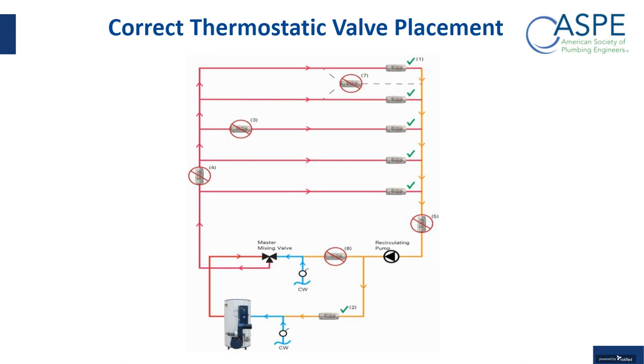The problem doing that with a thermostatic balancing valve is, as I said multiple times, it's a temperature device. What will happen if, for instance, you put a thermostatic balancing valve at the output of a pump? As soon as it starts seeing that higher return temperature, what's going to happen? That valve will start shutting down. It's going to start basically limiting the flow out of the pump. So again, and I'm sure you'll be able to get a copy of this presentation, it's really key to make sure you don't put thermostatic balancing valves in any of these locations that aren't a traditional location for a balancing valve. So this is an important point to keep in mind.